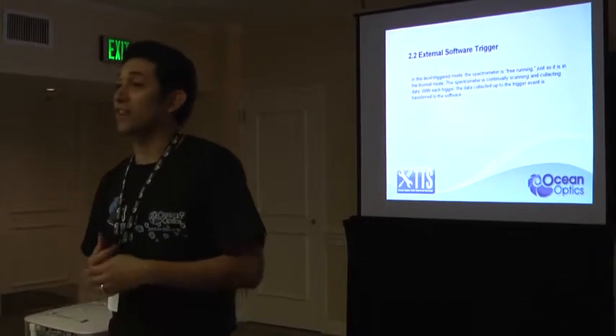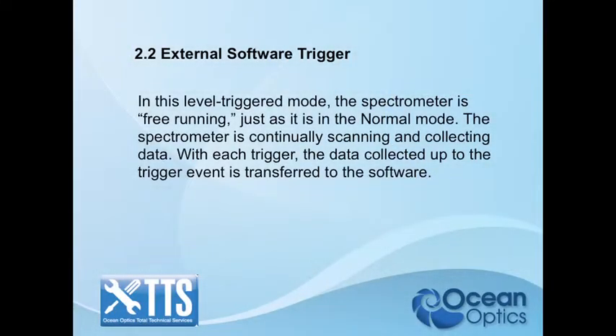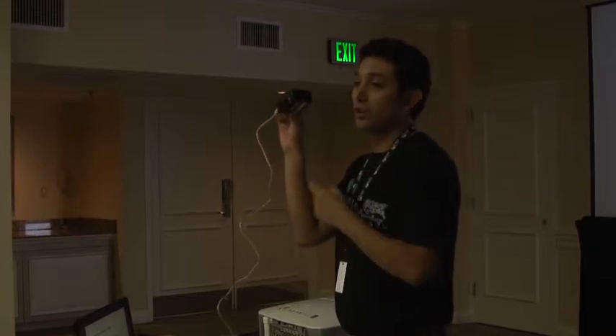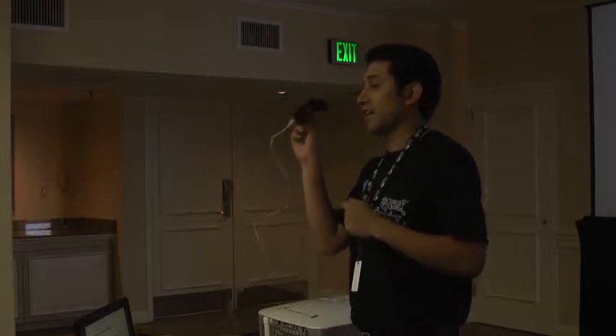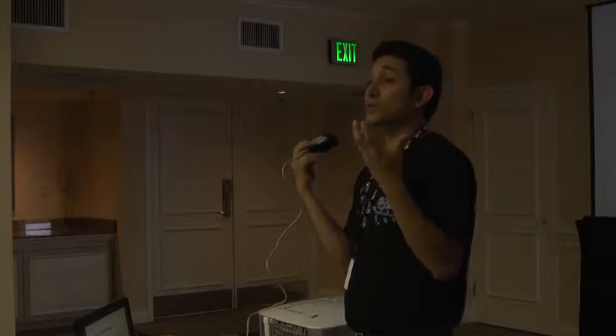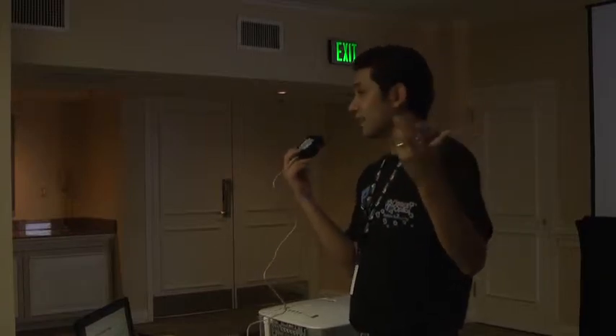The next trigger mode is called external software trigger. It's a little bit confusing because it seems like you are triggering the spectrometer with software, but that's not what's happening. You actually need to provide a five-volt TTL signal into your spectrometer. For example, the USB 4000 has 22 pins, the HR 4000 family has 32, and the old USB 2000 had 10 — but one of those pins is your external trigger input.